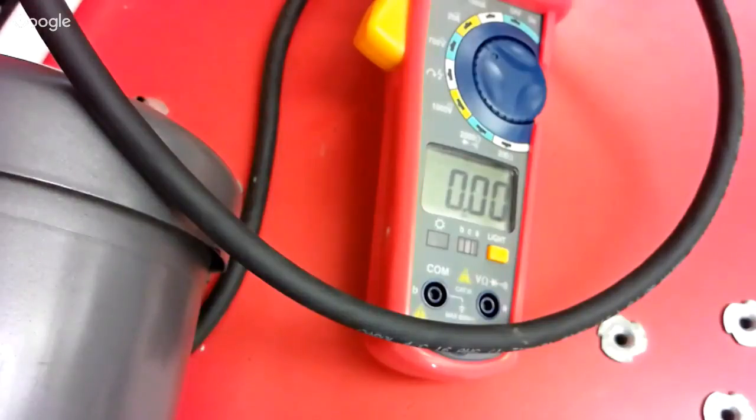Of course, that depends on the meter. If I were to pick 2 phases, I can read something. But because I'm reading all 3 phases, the EM fields cancel one another out, and I don't get anything. So it's not accurate.